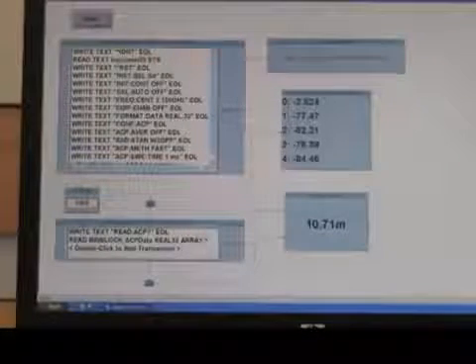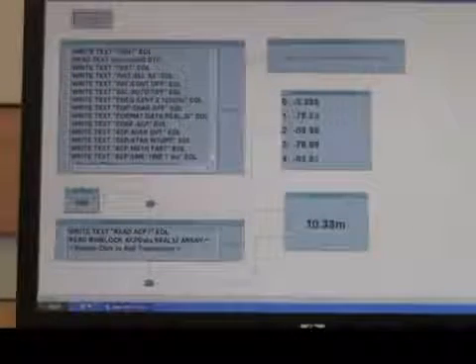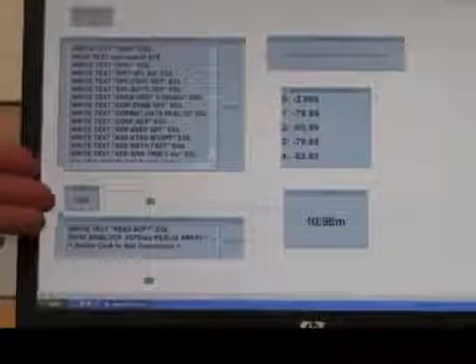Let's go ahead and start the measurement. So now we're running through this sequence 1,000 times. As you can see, we're updating the channel power levels here. We're achieving over 81 dB of dynamic range.